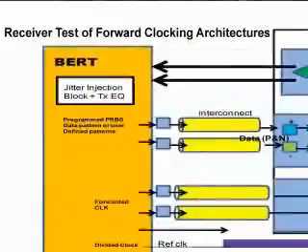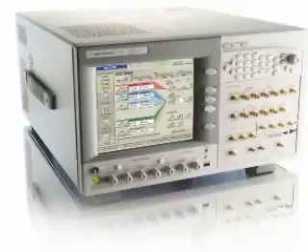These kinds of devices require very special testing capabilities. The generator not only has to provide stress data signals, but also stress on the clock signals. And the new J-BERT has all these new capabilities that support testing of such forwarded clock devices.